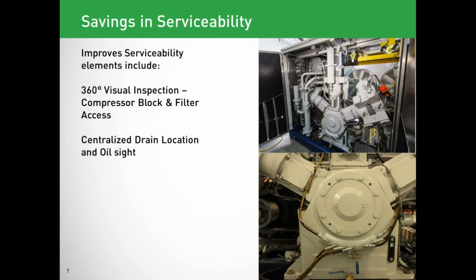In the lower photo, you can see right under the circular cover plate, there's a tubular drain location where all of the bottle drains and vents drain into, with a main drain valve at the bottom, a quarter-inch ball valve. This allows any condensates or any liquids in the fuel stream that get trapped in the scrubber bottles to be drained into this central location. This location is accessible by opening the air intake louvers, and this vent header can be drained on a regular basis very easily. In addition, the oil level gauge is located on the right-hand side of the compressor block. It's that rectangular device with the oil level showing. This allows much easier visibility of the oil level and the ability to top up the oil as required well before it poses a maintenance issue.